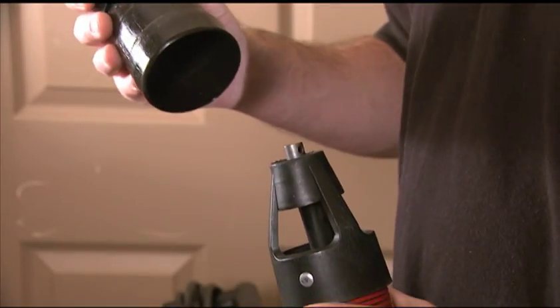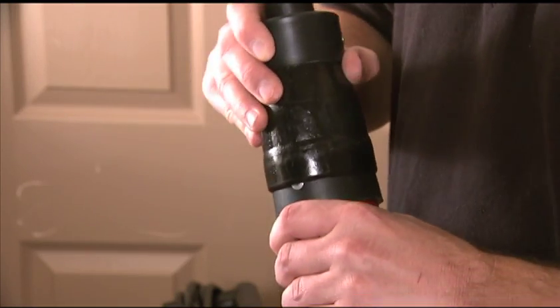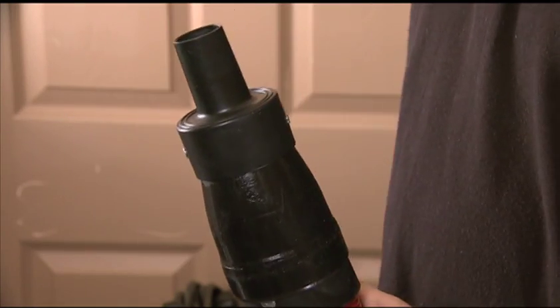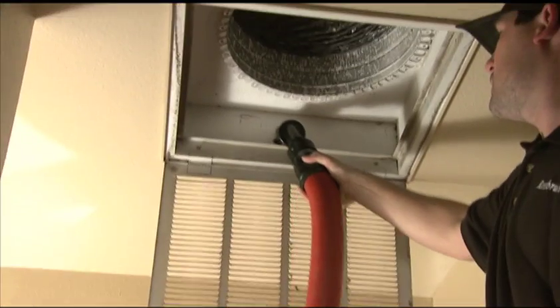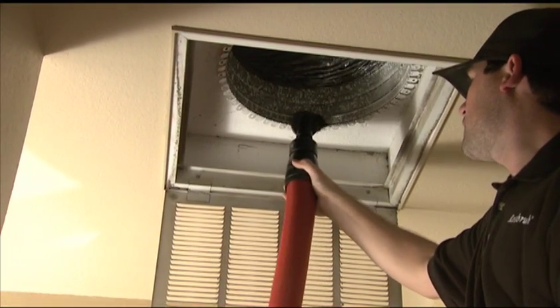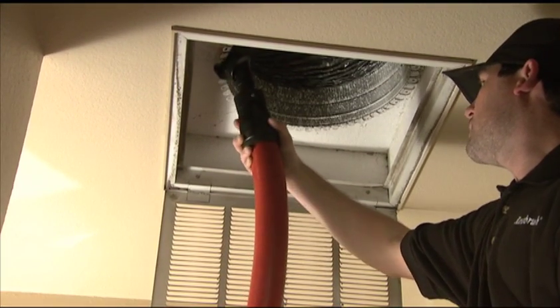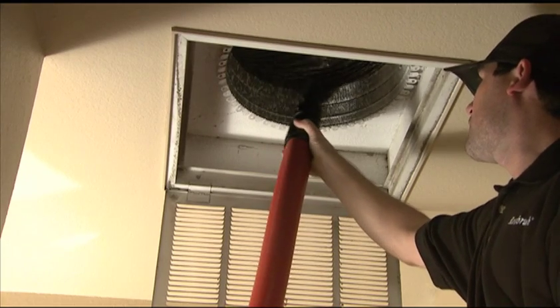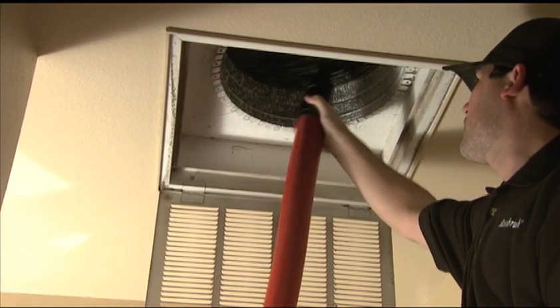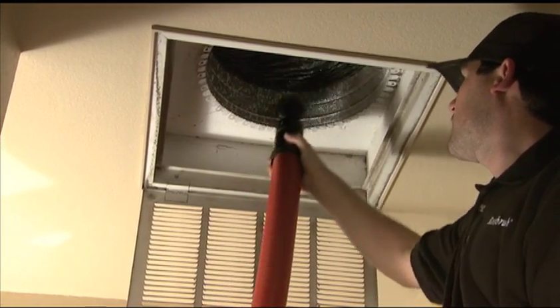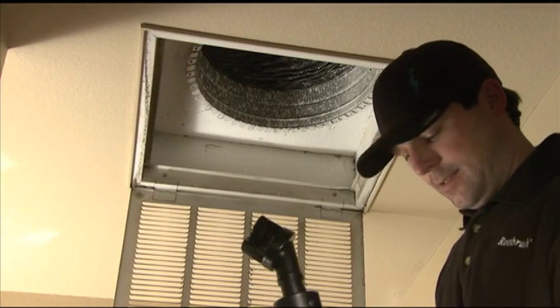If the registers are not heavily soiled, use the Rotobrush nozzle adapter and dust brush to vacuum. You may also use a HEPA-filtered shop vac. Also, vacuum out the boot area, cleaning the air duct as far as you can prior to cleaning with the Rotobrush. If you determine the register covers are going to need more aggressive cleaning, go through the house and remove those and take them outside to clean.